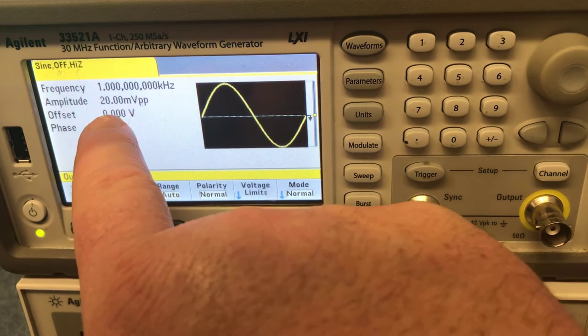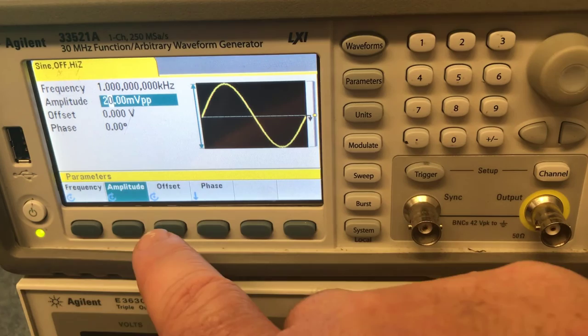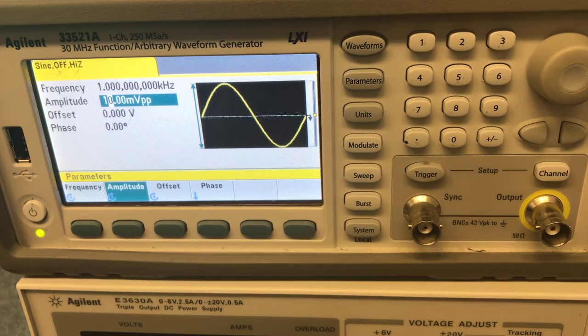Now, you'll notice that it actually went ahead and adjusted that up to 20 millivolts peak to peak. So we need to go in and adjust that again. So let's go to parameters, amplitude, and then I can take that down to 10. And so now we're good.